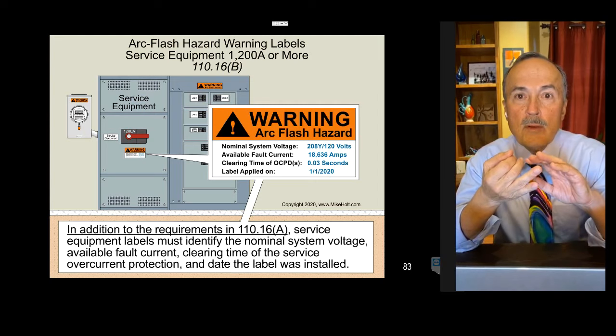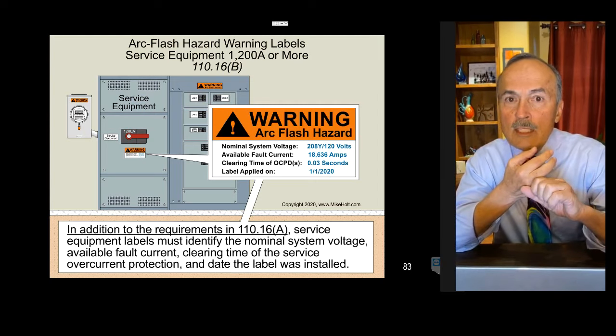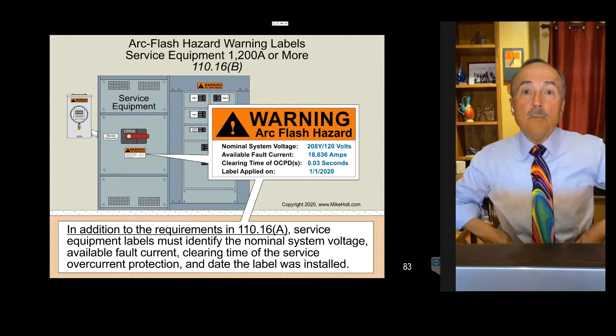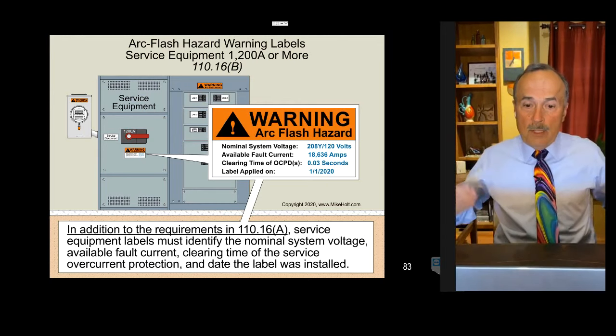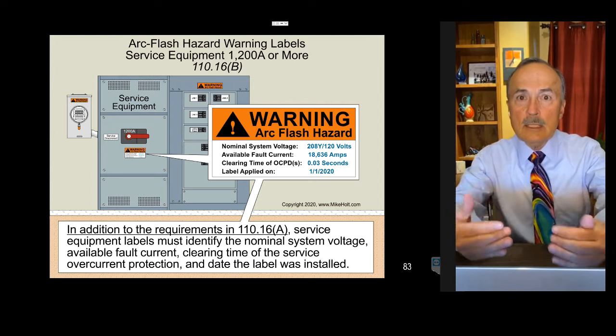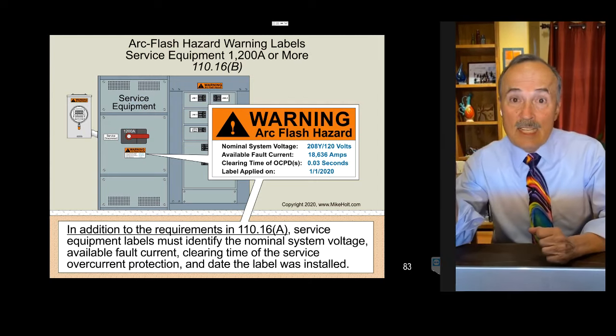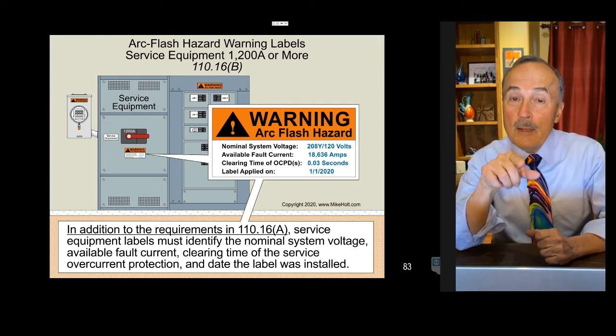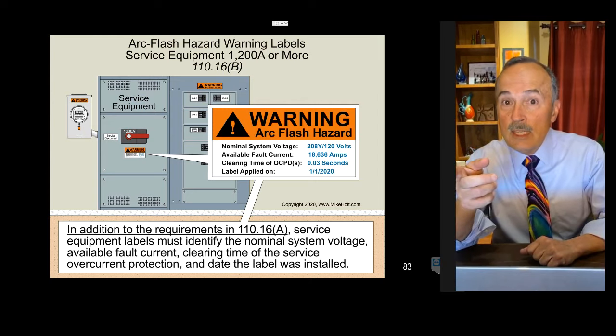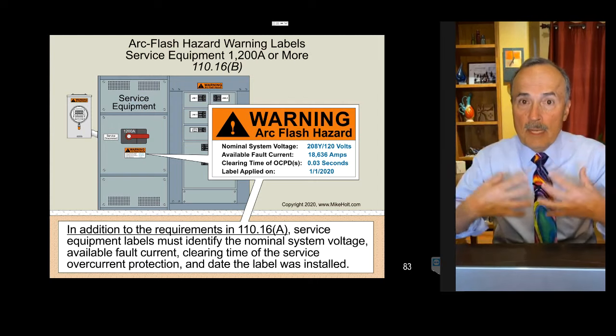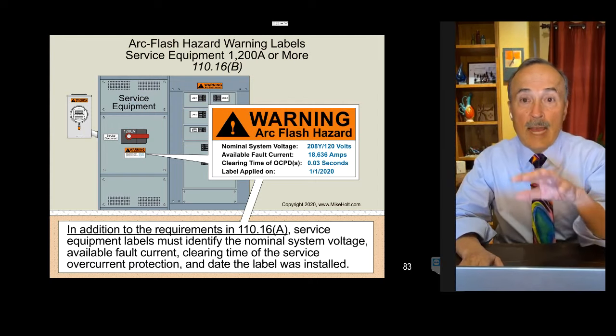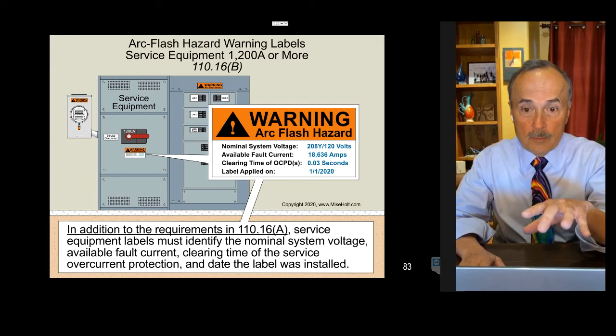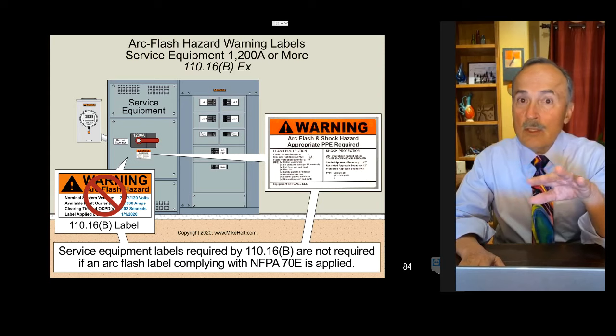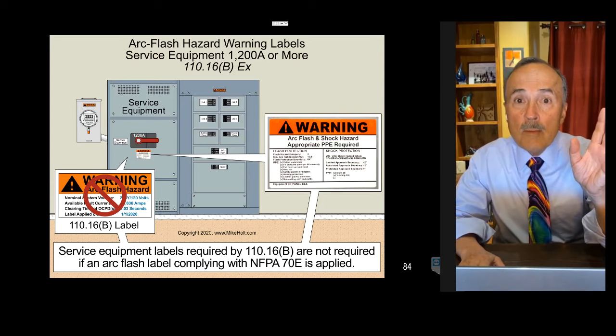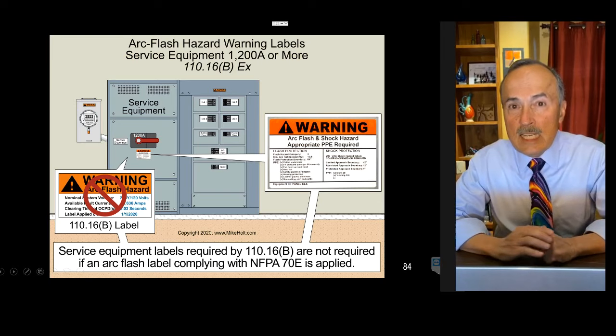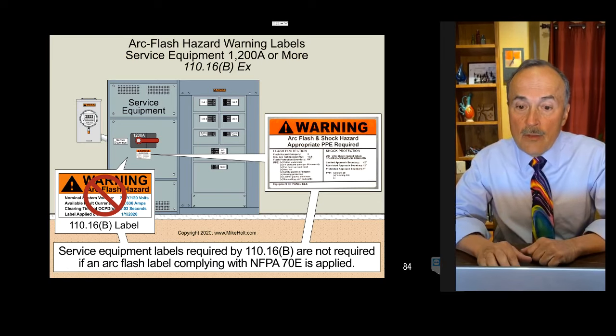See, because the code cannot require you to put an NFPA 70E label that will tell you the incident energy calories, any of the blast zones, arc flash zones, so that a person knows, okay, here's the protective gear I have to put on. And when I get within this area here, I have to do this. Well, the code can't, that's a 70E requirement, but the code can just say, okay, fine. But guess what? If you have that information, then you can go to 70E and you can extrapolate out what kind of PPE equipment that you should be using. Now that is services, 1200 amperes or more.